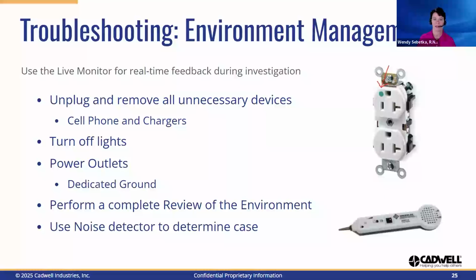Troubleshooting the environment can be as easy as flipping off a light switch or as difficult as having to seek out an electrical engineer to test the integrity of your earth ground. When troubleshooting through environmental concerns, unplugging all unnecessary devices one by one will allow you to rule out or localize a concern. Temporarily turning the lights off or unplugging devices will provide real-time feedback regarding the contributions to that particular device. Just because power outlets are in the same room doesn't automatically mean they're on the same circuit.